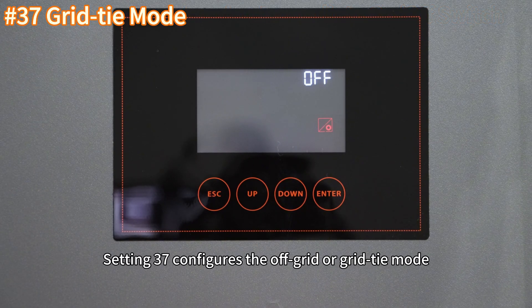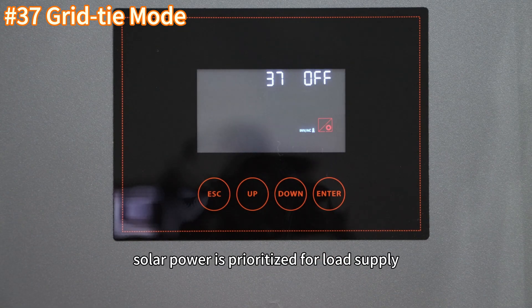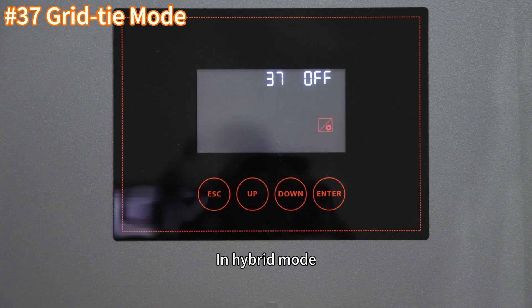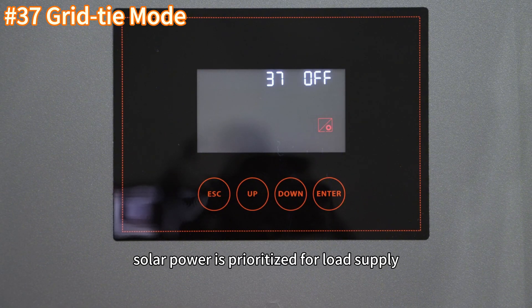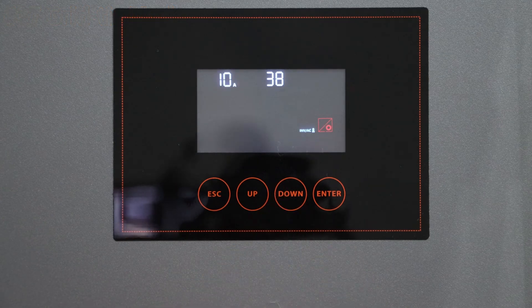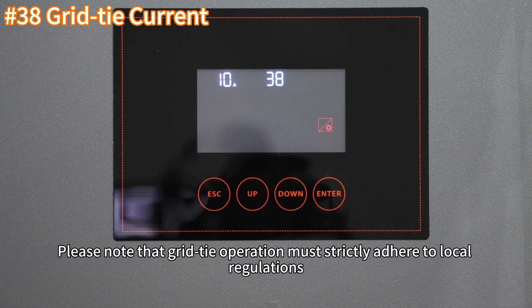Setting 37 configures the off-grid or grid-tie mode, with off-grid as the default. In hybrid mode, solar power is prioritized for load supply, followed by battery charging, with excess power fed into the grid. Setting 38 configures the grid-tie current. Please note that grid-tie operation must strictly adhere to local regulations.